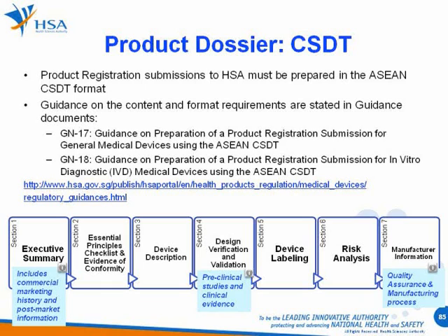For Section 3, it is the device description on its principles of operation, intended use, instructions for use, list of constituent materials. Section 4 is the design, verification, and validation. Data collected from preclinical studies and clinical data gathered from literature review of existing bibliography and/or clinical investigation.